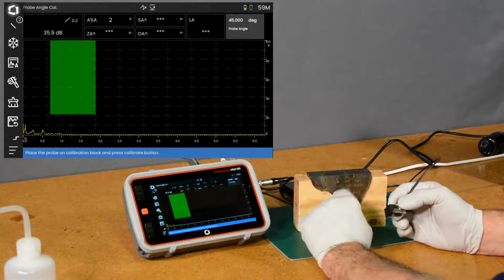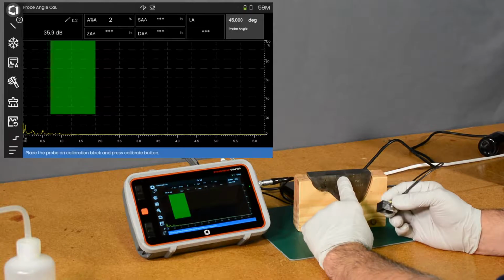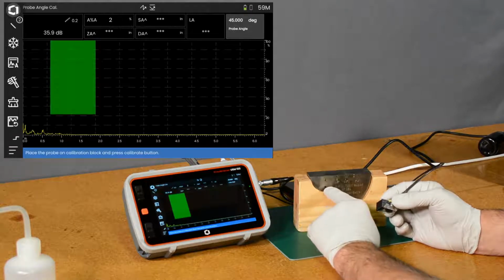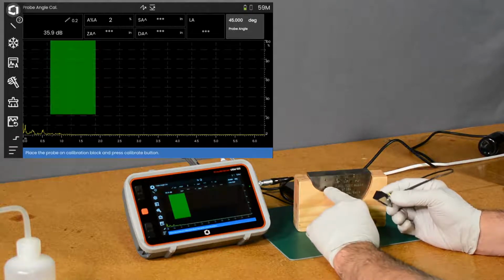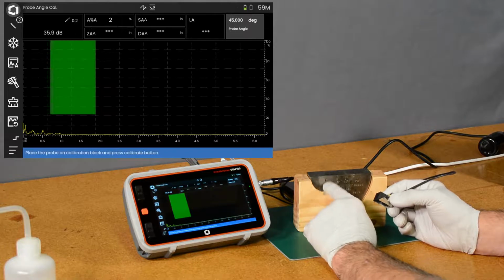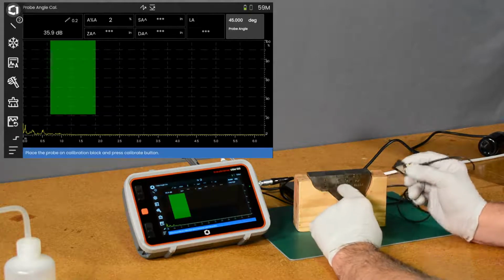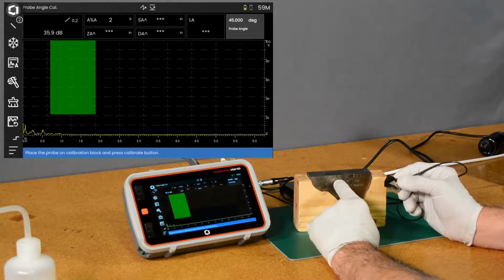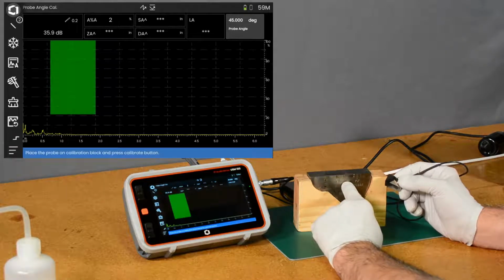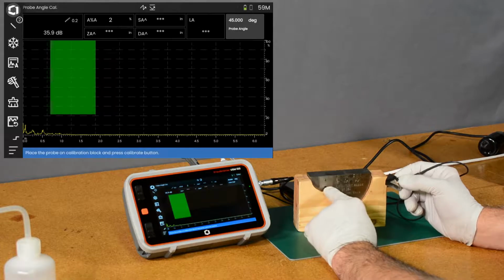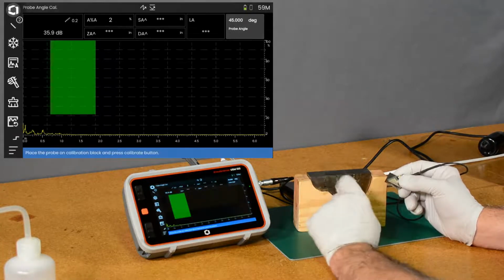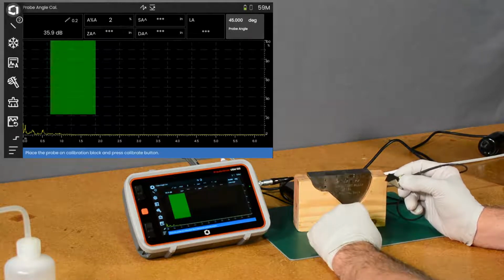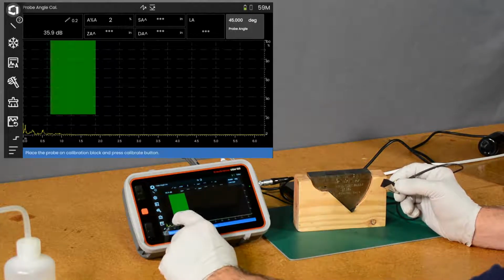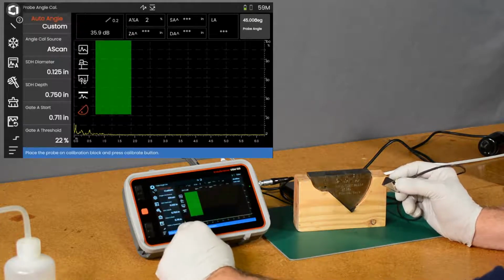So I have a DSC block here for reference. The DSC block gives us a 1/8 inch diameter side drilled hole, 3/4 of an inch deep in the block. And then it also conveniently gives us some reference index marks here at 45, 60, and 70 degrees with respect to that hole. So it helps us set up a little bit for this test. So let's open our calibration menu.